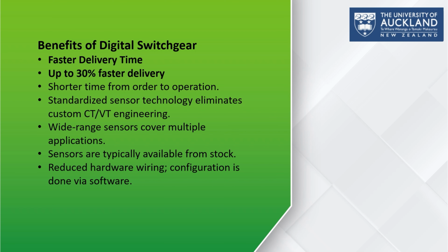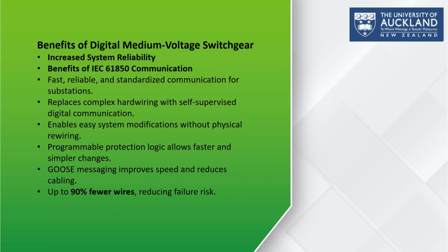So this improvement is driven largely by the use of IEC 61850 communication, which is a global standard for substation communication. In traditional switchgear design, we need a large number of wires running between cubicles to exchange signals. So this is not only makes the system complex, but also increases installation time and failure points. With digital switchgear, all the information is transmitted through a self-supervised communication cable, right? So this drastically simplifies the interconnection between cubicles.